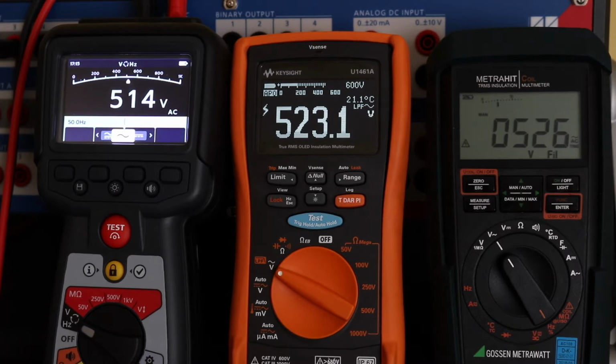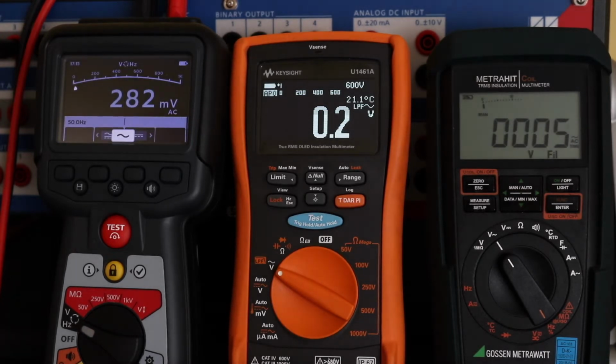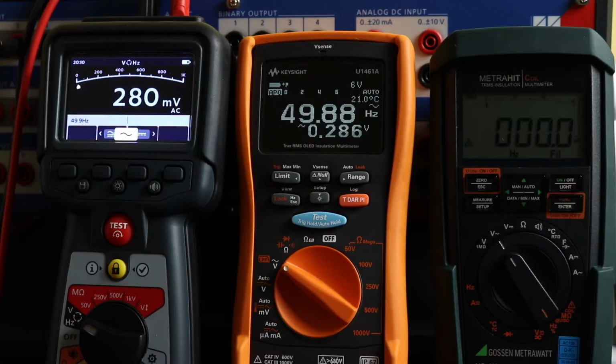And what you do tend to notice is that the Megger is lagging behind the other two instruments by quite a noticeable amount, which is not good. Accuracy wise I don't think there's any issue with it, but its response, I guess for the instrument just aimed at measuring voltages on a motor, it's acceptable for a single capture, which I guess is what it's intended for, but the slow speed of the response did surprise me.